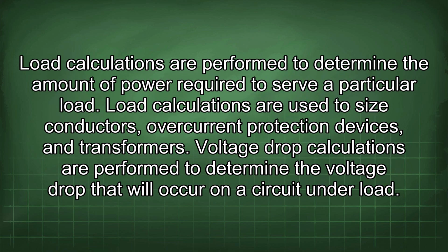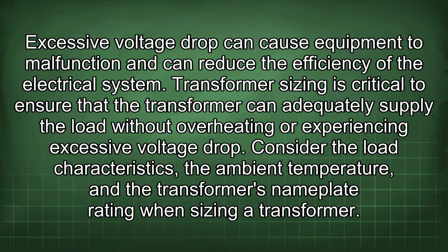Load calculations are performed to determine the amount of power required to serve a particular load. Load calculations are used to size conductors, overcurrent protection devices, and transformers. Voltage drop calculations are performed to determine the voltage drop that will occur on a circuit under load. Excessive voltage drop can cause equipment to malfunction and can reduce the efficiency of the electrical system.